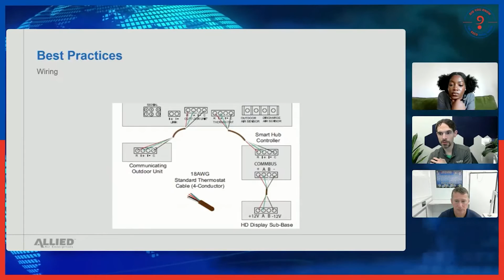So my wire may be fine, but how it's routed could be the issue, and when that big piece of whatever accessory comes on, it seeps in. In that case, we could jump into how it's wired itself. A good example, like we talked about, is separating your communicating wiring from your power. That's probably the top way we recommend running it, especially with our 4-wire setup. You can have all 4 together, and people have luck with that as well, but sometimes you have to break it all the way down to actually shielded wiring, which could be a whole other discussion.